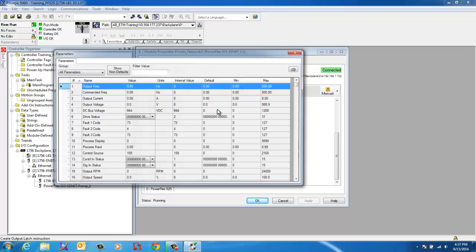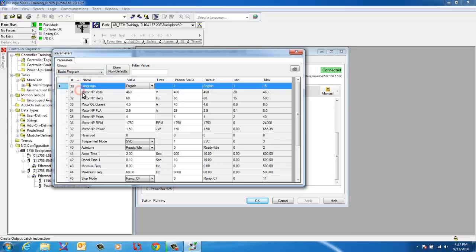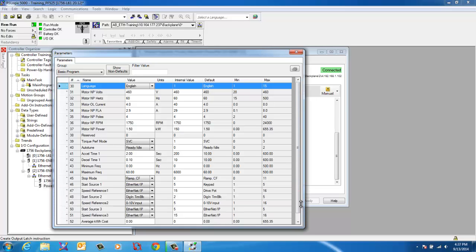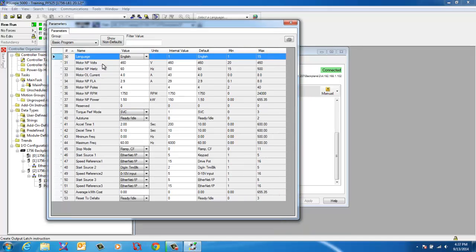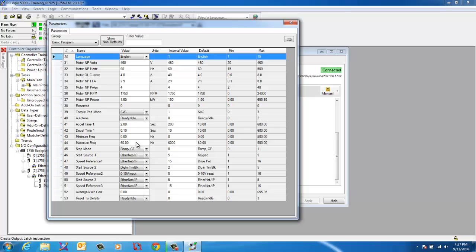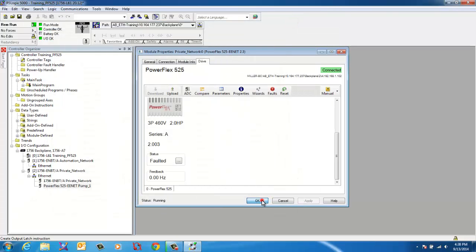So go to parameters. Easiest way to set these up quickly online, use the drop down list. Go to basic program. Now the basic program will have all your basic parameters that you really need to change. Pull them all out. Match your motor. Your acceleration time. Your decel time. If you want no decel time I advise you to put in 0.10. That will help keep your drive from faulting. There may be some other things you can do. But that's what I found. And that's what Rockwell's site had suggested at one time or another. My stop mode is at ramp. So I'm ramping down. I put that on coast. Start source. This is what you'll change. I believe out of the box it will be set on digital and on the terminal block. When we change it to Ethernet IP, then we want our speed reference in Ethernet IP. Minimum frequency. Maximum frequency. And these are all things you need to change just to do a simple setup. Anything else is on you. Everything looks fine there.